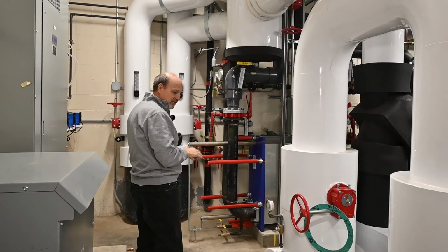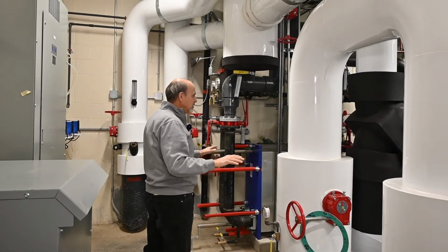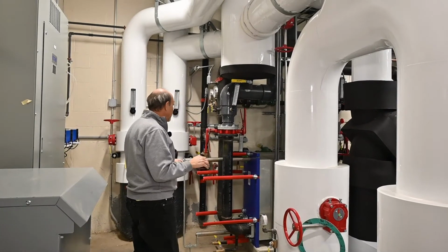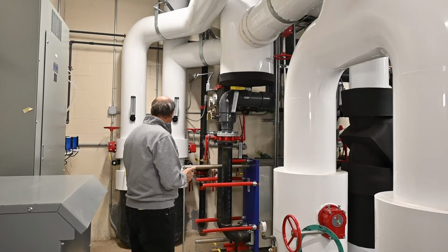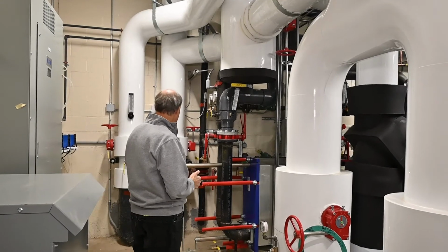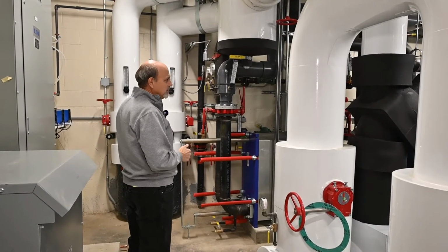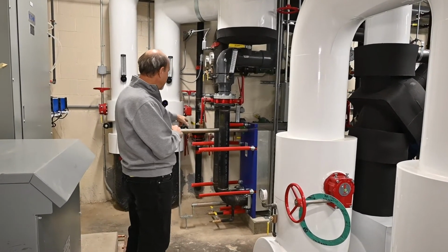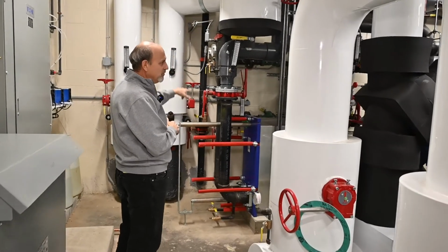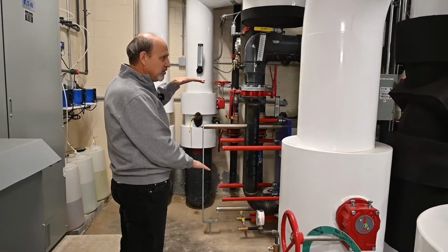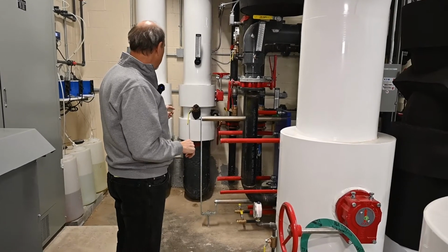And then the entire floor is going to get painted as well. So we've still got some work in here left to do, but that'll be ongoing. So in a nutshell, there's two different systems here. There's an 8-inch main glycol system, which is your cold floor, and there's a 3-inch glycol system, which is your warm floor. Obviously, the warm floor is below the cold floor. So I'll start with the cold floor piping.